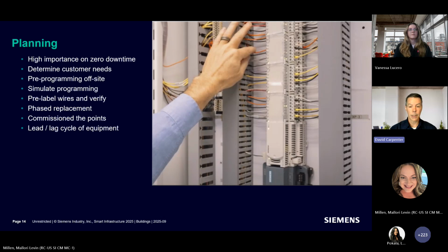This meant it was ready to go. Once it was in the panel, another tool that ABT with Siemens software has is we can commission every single point, and it produces a commissioning report for peace of mind for the customer. This shows all of the facets of every point, what was commissioned, if there's any offsets, or if there's any problems with that point. That way in the future, there's no confusion about anything that physically went in.